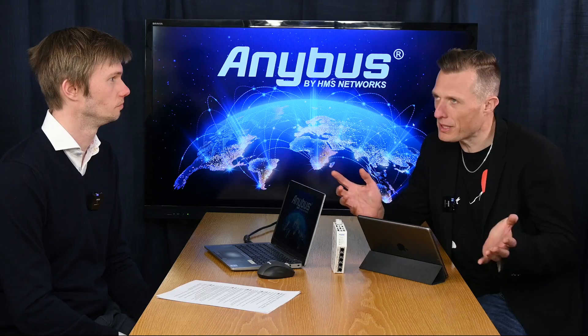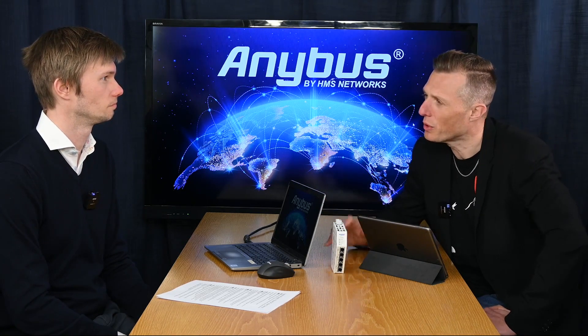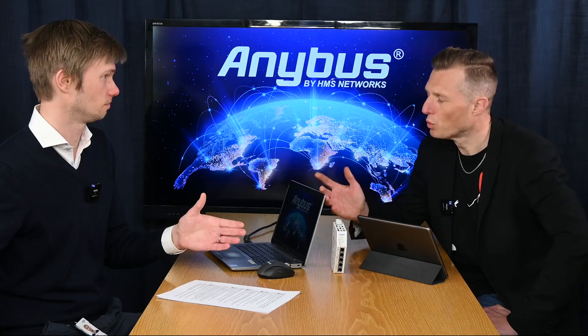Let's look at a scenario. Say you're a device manufacturer or machine builder and you want to deploy 10 different machines. First you do a reference setup — which you normally have anyway — then you scan the network and do the entire configuration. You export that configuration file and import it to the remaining nine devices. So you do it once and then you can just copy that configuration, helping the automation engineer.